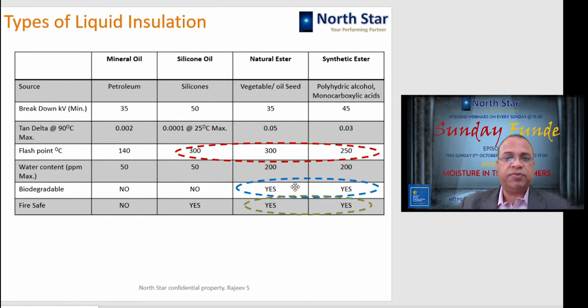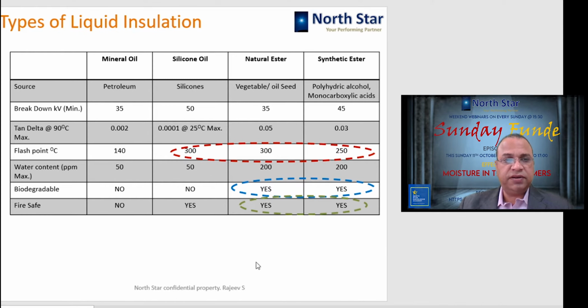Okay, so different types of liquid insulations are available. Mainly four types are available. Mineral oil, we all know, is petroleum based, and its minimum breakdown strength is 35 kV, and its flash point is 140 degrees centigrade. It is not biodegradable and it is not fire safe.